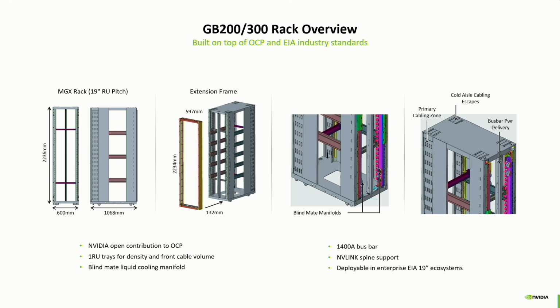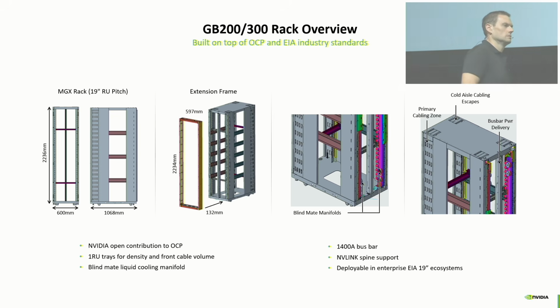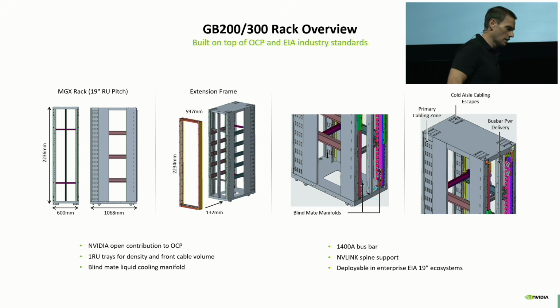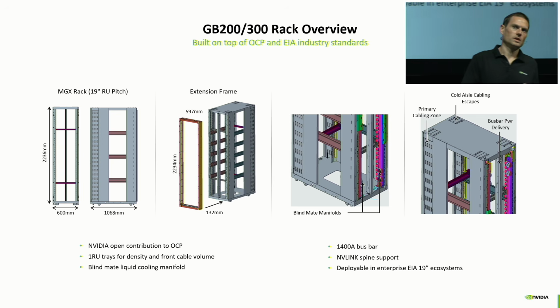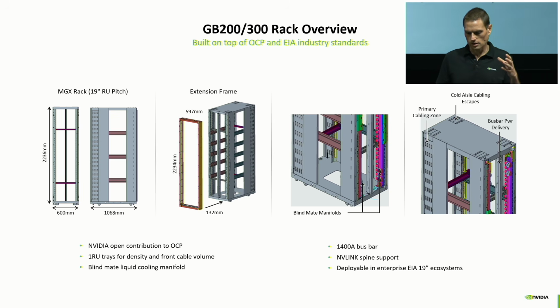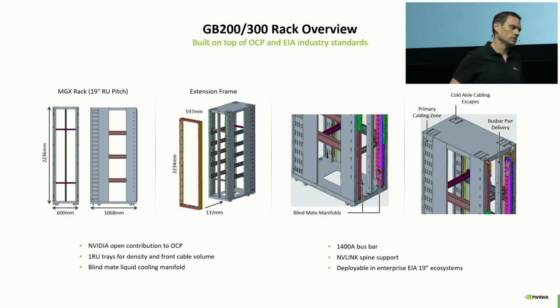I want to talk about some more detail on the rack. I mentioned this was contributed to OCP - that's actually where we started. The MGX rack started life as an ORV3 rack. ORV3 is an open rack standard established in the Open Compute Project, OCP, and there were a lot of elements of that we really liked. We liked the rear blind-mate power - that was an existing feature of that rack. We also liked the serviceability aspects: the front cabling, cold aisle access. You can service most of the rack without ever going into the hot aisle.